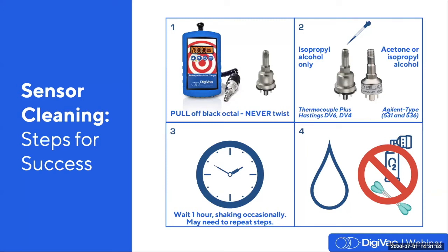Take a pipette or small funnel and pour about a tablespoon of your solvent of choice directly into the body of the sensor, and allow the sensor to stand upright and let the solvent do its work and dissolve the contaminants inside the body of the sensor. Waiting approximately an hour, you'll want to pick up the sensor a couple of times. Just put your finger over the opening and very gently agitate and shake it to ensure that the solvent is moving around. Once your hour's up, you can go ahead and pour the now contaminant-rich solvent out, and you may need to repeat this step possibly once or twice, depending on how contaminated the sensor is, until the solvent runs clear from the body.